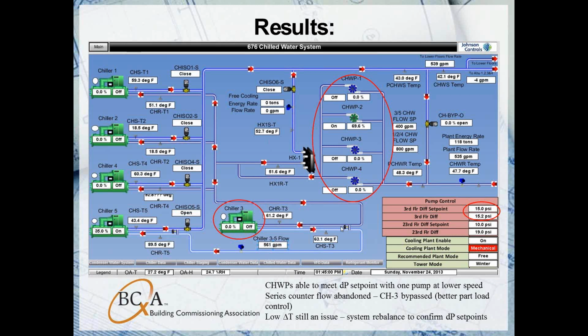We've valved it off. So we've abandoned the series counterflow setup here. And as an extra step to this project, we sought out a mechanical contractor to provide pricing to install automatic isolation valves on chiller 3 so that we could, in fact, include it in the overall chiller plant control strategy. But that would happen in the future. So right now, in the picture you're seeing here, it's just manually isolated, and we're using one 400-ton chiller as our primary stage of mechanical cooling.